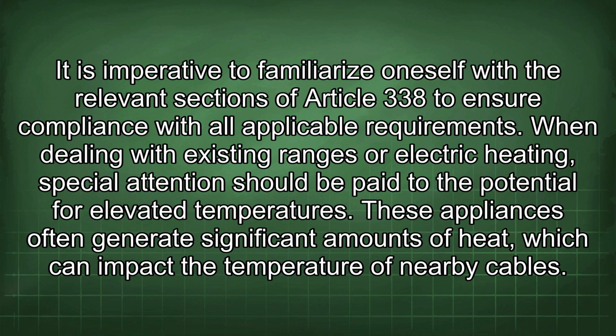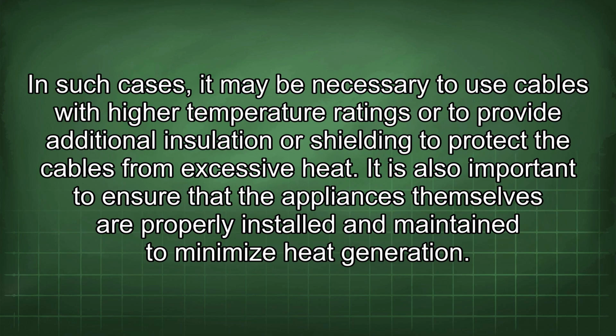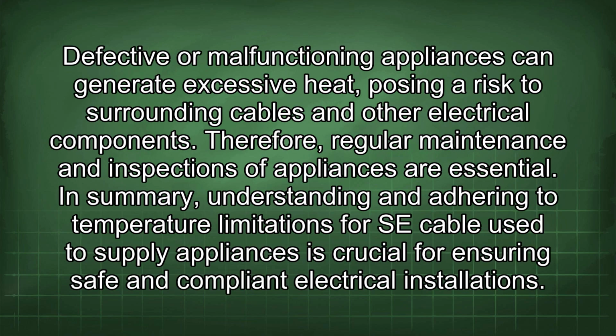When dealing with existing ranges or electric heating, special attention should be paid to the potential for elevated temperatures. These appliances often generate significant amounts of heat, which can impact the temperature of nearby cables. In such cases, it may be necessary to use cables with higher temperature ratings or to provide additional insulation or shielding to protect the cables from excessive heat. It is also important to ensure that the appliances themselves are properly installed and maintained to minimize heat generation. Defective or malfunctioning appliances can generate excessive heat, posing a risk to surrounding cables and other electrical components. Therefore, regular maintenance and inspections of appliances are essential.